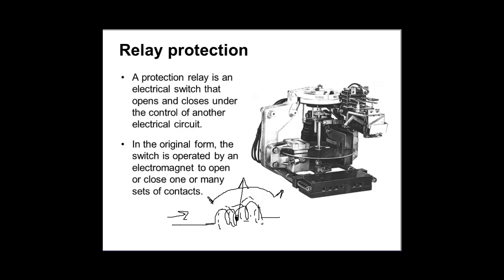That disc at the beginning is under the influence of N and S. Where is that N and S? It's in here. Look, see the magnet? It is in between in there. It's being stopped. It's a braking torque. The relay disc does not move. No fault. So what about if there's a fault? Aha! When there is a fault, we have got a coil, the trip coil. So the current goes into the coil. So there will be an electromagnetic field.